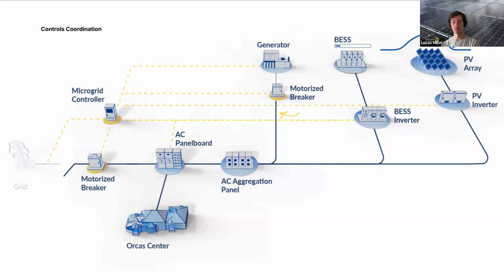So if the BESS state of charge falls below a certain level, we will tell this motorized breaker to close, and then the generator becomes our main power source. We're now powering the facility with the generator. We're also recharging the BESS with the generator. Once the BESS reaches a high state of charge, we open this motorized breaker and go back to the BESS as the primary power source. So from Mayfield's perspective as electrical engineer of record, I think this was the biggest challenge, all the coordination involved with relays, breakers, and determining the sequence of operations to make all of this work. But I'll kick it to you, Markus, and you, Aaron, to give us a little more flavor on what all went into this project.